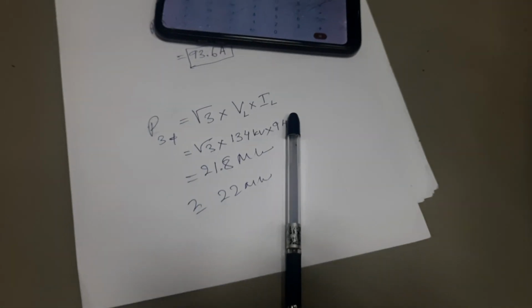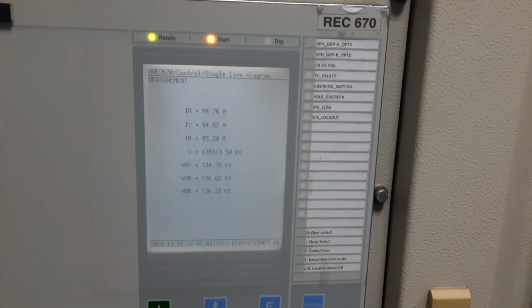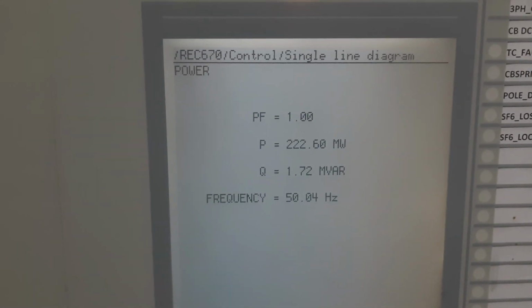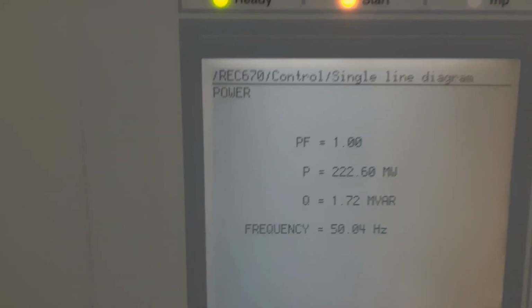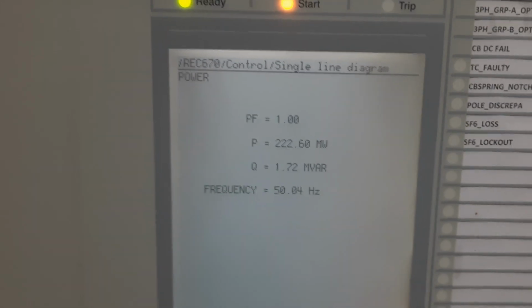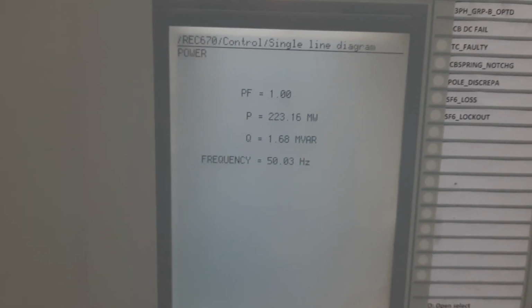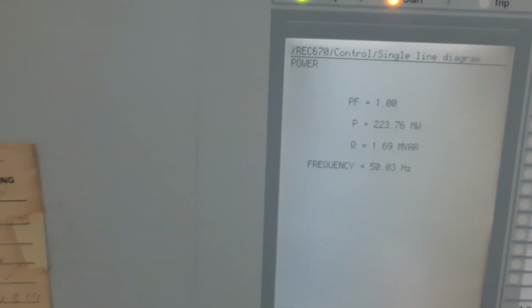Okay, so let us again check from the BCU whether it's giving this much megawatt or not. So let us go and check from the BCU. Your BCU should read 22. Okay, so it's giving you this power. See, this active power of 22.2 megawatt. Something is wrong in the relay setting, a factor of 10 has not been divided in the BCU. It's just program related, otherwise it's 22, because 223 is a huge power. Maybe I wouldn't need this much power during daytime, especially nighttime maybe this much, but it's very rare that they require this much megawatt. So it will be 22.